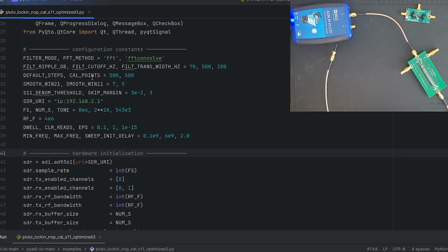First, we defined the rejection we want out of the low pass filter, the cutoff frequency, the transition width of the filter. Then we define the number of measurement steps we want to do in the frequency sweep, or the number of calibration points we want to do. Also, there are some smoothing filter constants added here, which are basically to smooth the plotted S11 or S21 data. Also, then the sampling frequency, the number of samples we take each time, the tone of the transmitter, and also the minimum and maximum frequency in the sweep.